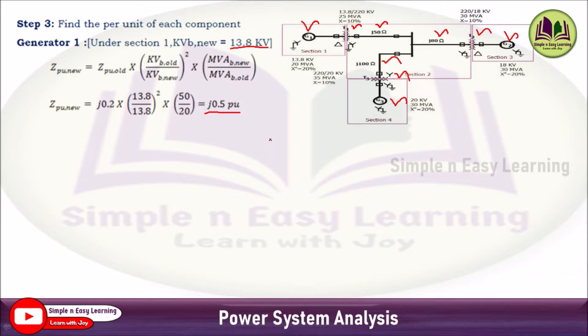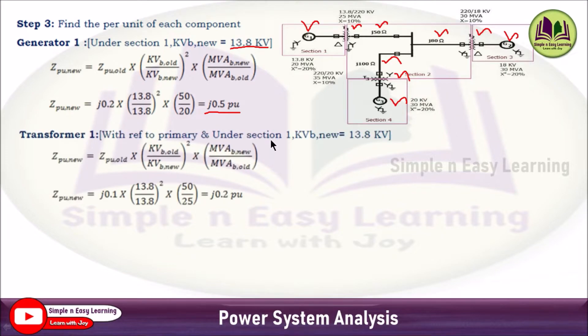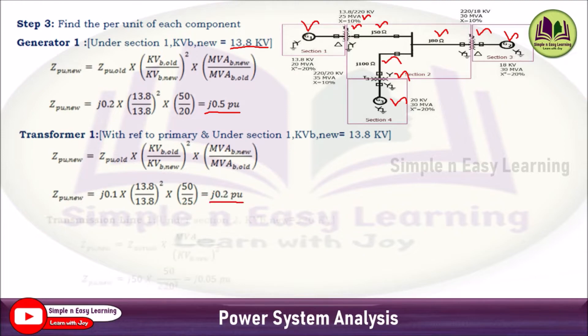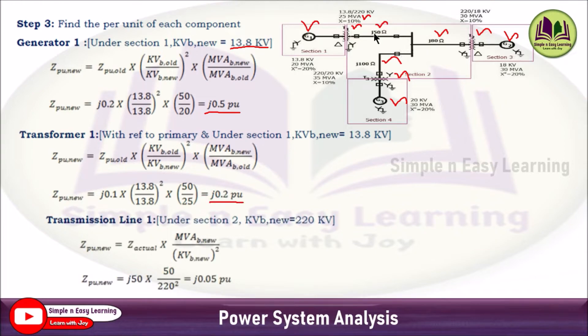Similarly, for transformer T1 referred to the primary side (section 1, base kV = 13.8 kV): Z_pu_new = j0.1 × (13.8/13.8)² × (50/25) = j0.2 per unit. For transmission line 1 in section 2 (j50 ohm), use Z_pu = Z_actual × MVAB_new / KVB_new²: j50 × 50/220² = j0.05 per unit.